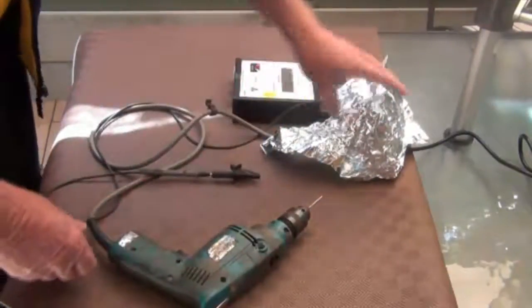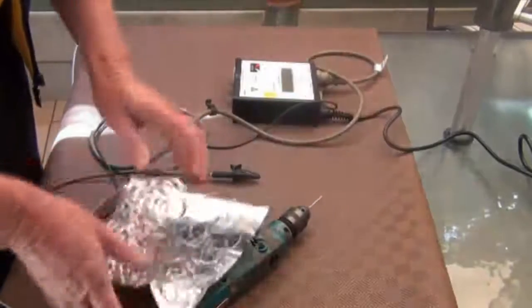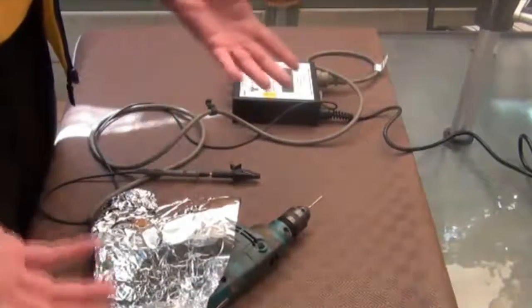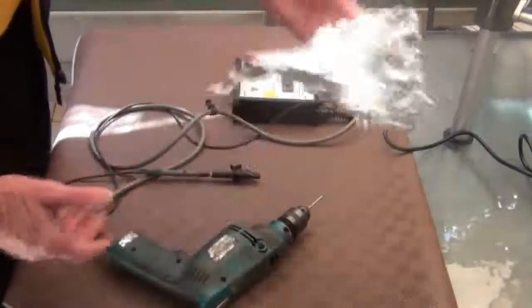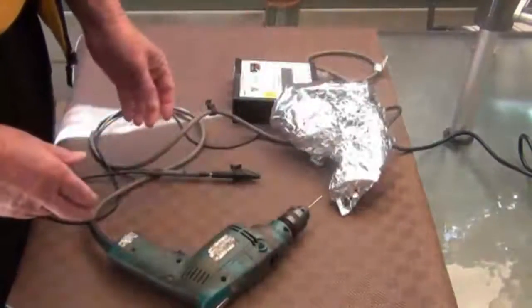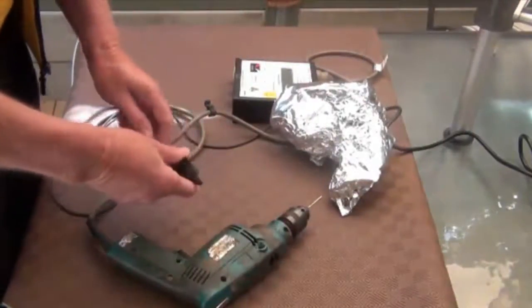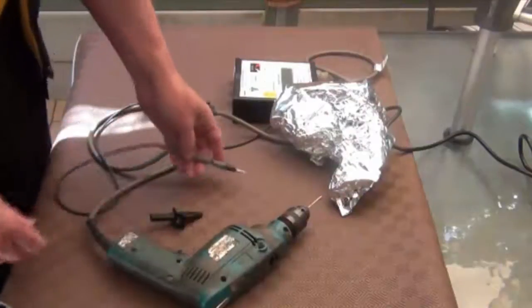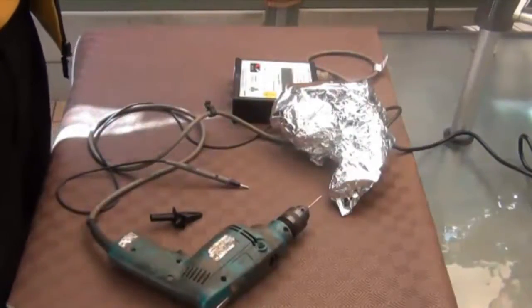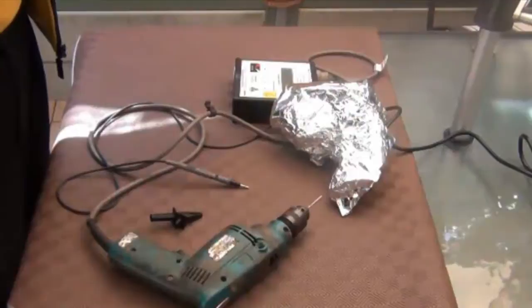I have seen people just wrap this around the plastic and that's the end of the test. That does not replace using your probe to any exposed metal. You can use it with either the run test or the insulation resistance test. It really is your own preference.